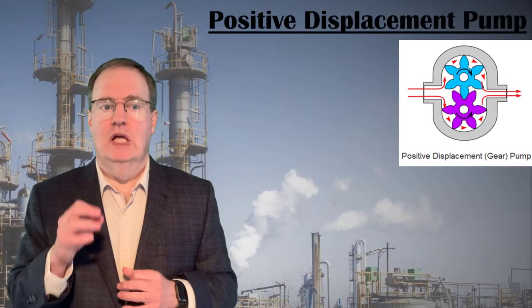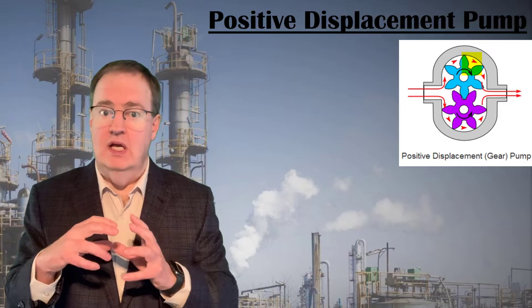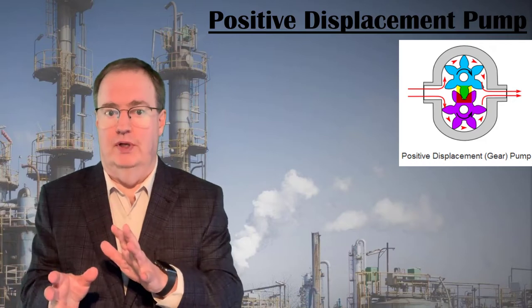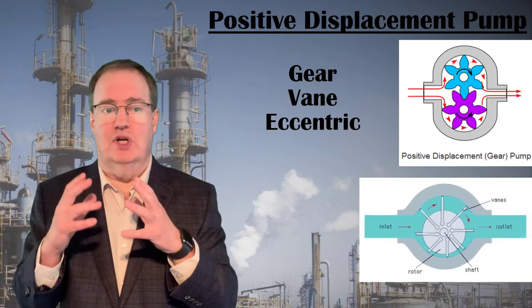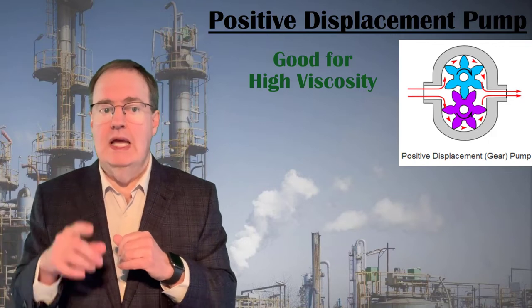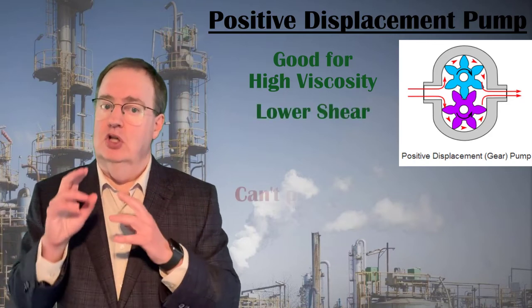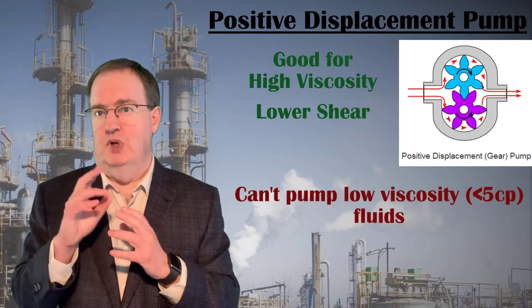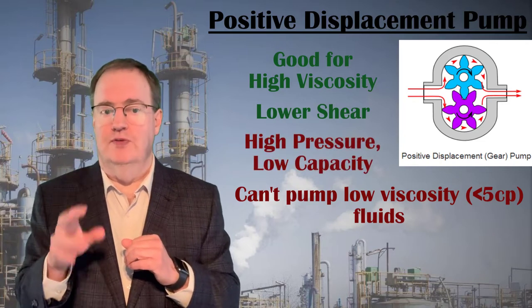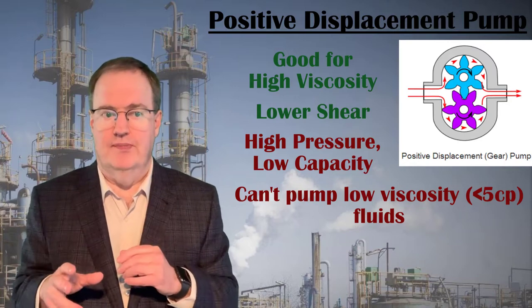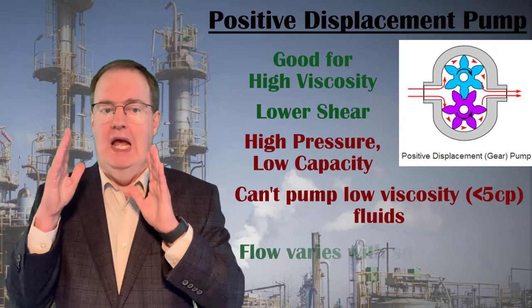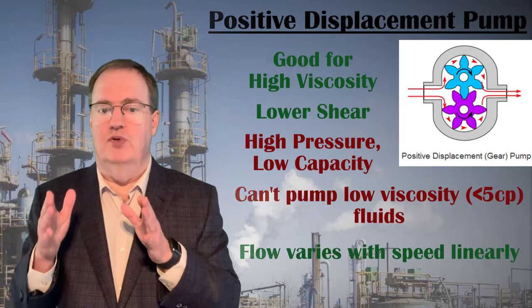A positive displacement pump creates a cavity at the feed point, seals that cavity, and displaces it to the exit point, then makes the cavity shrink or disappear to push out the fluid — shown here as a gear pump, but vane pumps and eccentric rotary pumps operate the same way. Positive displacement pumps handle high-viscosity fluids well and are relatively low shear, but low-viscosity fluids slip past the gears or vanes. PD pumps can generate higher pressures but lower flows than similar-sized and priced centrifugal pumps. Their pump curves are essentially rectangular, delivering constant flow for any pressure, and the flow delivered will be linear with pump speed for a variable speed pump.